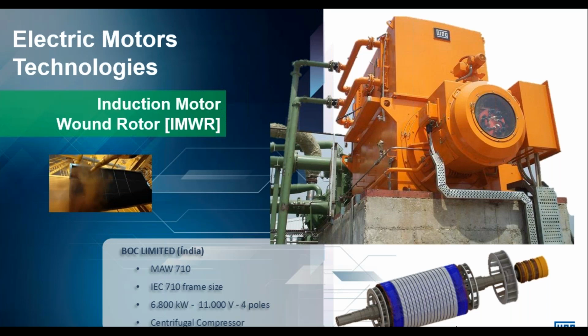So our service team went to site and attended to a slip ring machine in Saudi Arabia, a very, very large slip ring machine. It had multiple sets of brushes per slip ring, I think 11 brushes per slip ring. And this machine was not equipped with a brush lifting device. In other words, the brushes were fixed. So after startup, they did not lift or remove the brushes from the circuit. They operated this continuously, brushes fixed. The brush wear was approximately 10 millimeters per 1,000 hours, which seems pretty reasonable. That's approximately 10 millimeters every 40 days.